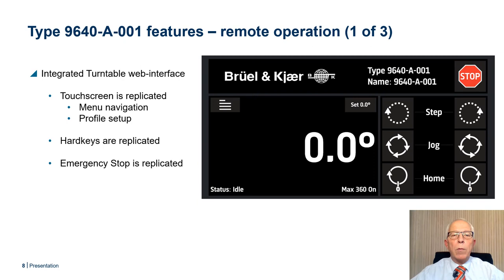Moving on to remote operation of the turntable. Here we have the integrated turntable web interface. The web interface has been designed to replicate the manual operation on the front panel, holding the menu navigation and profile setup available on the front panel. Likewise, the hard keys are replicated from the front panel, and a stop function is also provided.